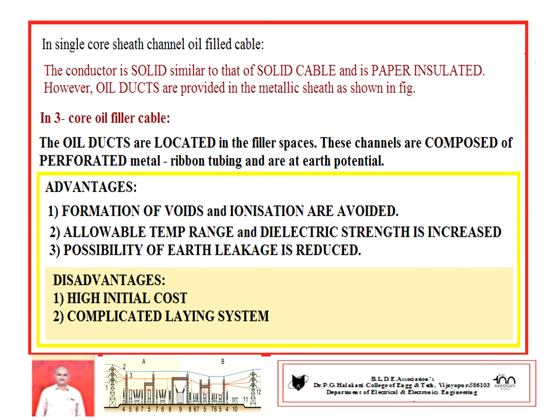The same point we have already discussed, sir. For different pressure arrangements of channels and ducts, you can refer to that only. There are so many advantages. Formation of voids and ionization are avoided. Allowable temperature rise and dielectric strength are increased. If void formation decreases, it increases dielectric strength. Then the possibility of earth leakage is also reduced.